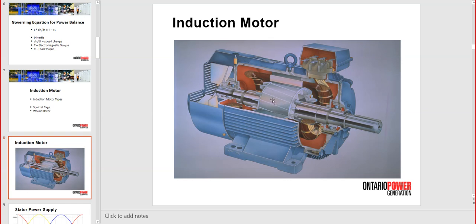Now this motor will have high efficiency, as the name says, and a high power factor, but it will have less losses and less starting torque. So be careful with the usage of high efficiency motors. It may not be the best. And yes, as far as I know, we replaced those motors in our plant for the fueling machine, and that needs to be done with reconsideration of the starting torque and the possibility of having to recalibrate the VFD for that application, because an on-the-shelf motor will not be so sensitive in the vector control the way a high efficiency motor is.